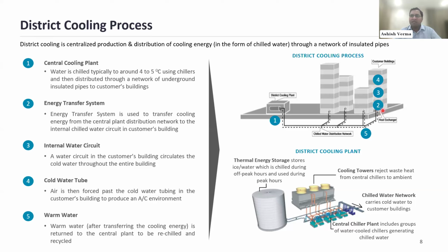In case there is an issue at the building level, it should not impact the district cooling system as a whole, because reliability is very important for district cooling plants, as multiple customers are being served. The building will have its own internal chilled water circuit, circulating chilled water to the respective air handling units. The air handling units take the warm air coming from the air-conditioned space, cool it, and return it to the space. This internal water circuit gathers heat from the air and delivers it to the energy transfer station. From there, the warm water returns to the district cooling plant for further recooling. So this is a simple process of how a district cooling plant operates.